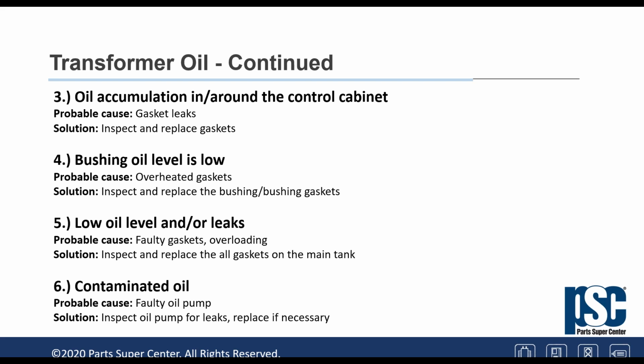Number 4, bushing oil level is low. The high voltage bushings are the ones that have a dome with the gauge on the dome, and usually they're yellow, and usually there's enough oil in there. But if that oil level decreases, this bushing, which is usually the ABB oil type O plus C or the old GE type U bushing, is sealed. In other words, at the bottom of the bushing, no oil from the main tank can go into the bushing. So if there is a low level in the bushing, most likely there's a leak in the bushing itself to be investigated.